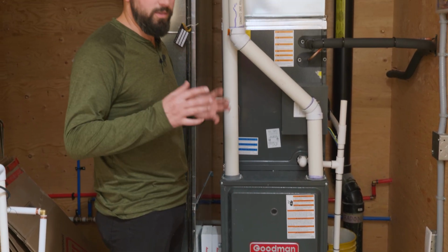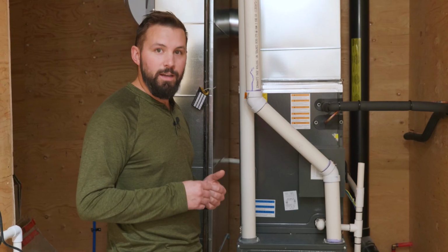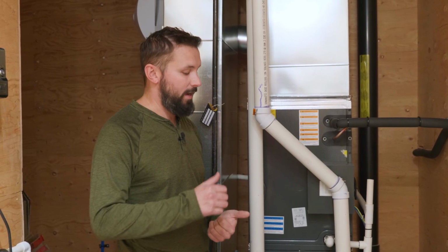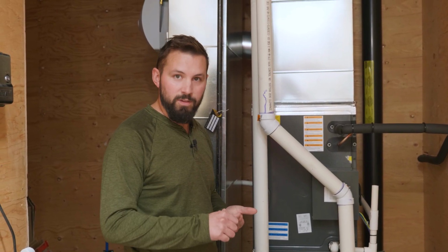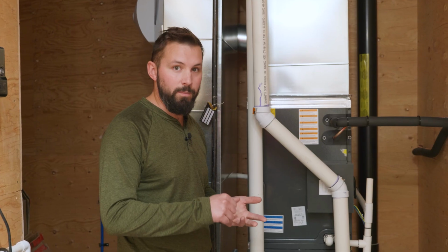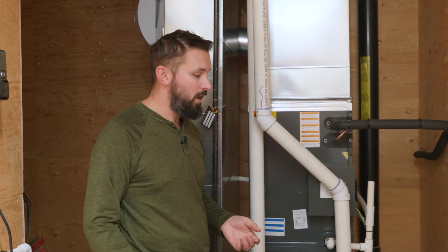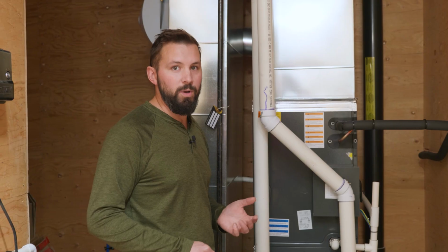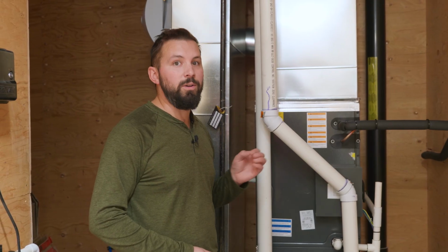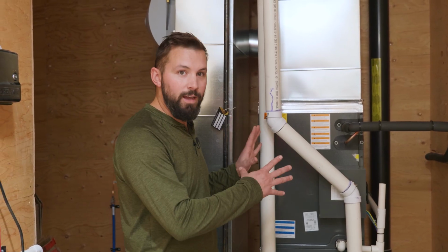The motor that powers the air around the house can be done in two different ways in modern equipment. We can have an ECM motor with different speed settings. You can have low, medium, high, or even sometimes 5 speed settings on an ECM motor, or you can have a continuously variable motor. Those are going to consume power in very different ways based on how the ducted system is designed and where we're putting the CFM.